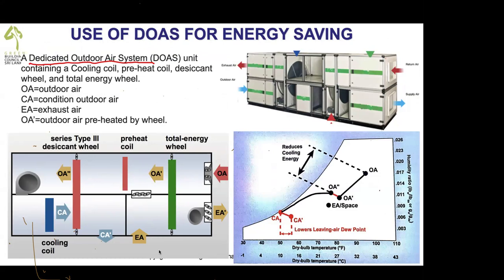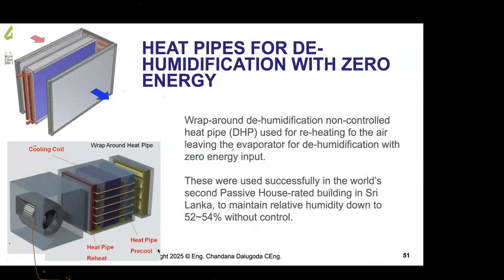For places like large arenas and large banquet halls, the outdoor air requirement is supplied by the DOA unit. The DOA unit has enthalpy wheels, one desiccant wheel and a total energy wheel. Ultimately, if you had 100% fresh air coming like this, you would have had this much enthalpy difference. But now it is reduced to this. You can understand. About 40% energy reduction.